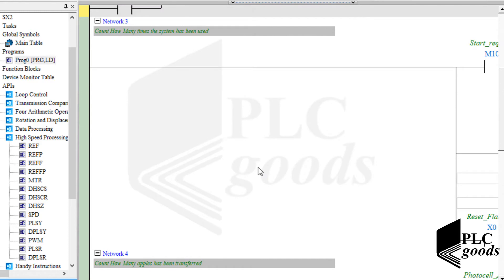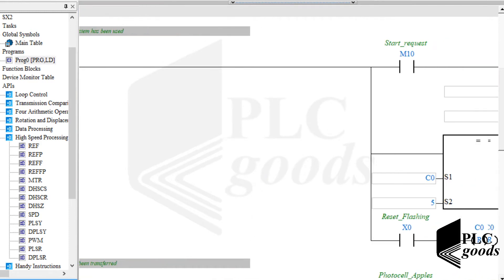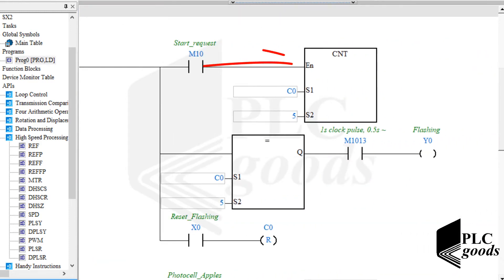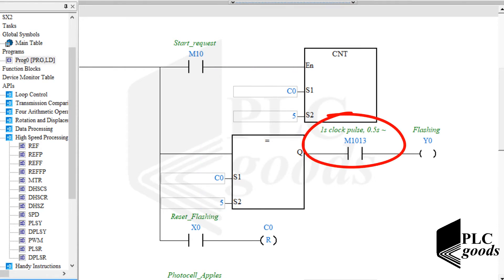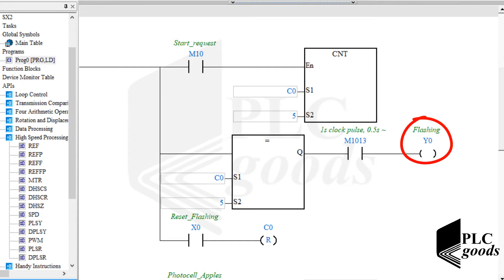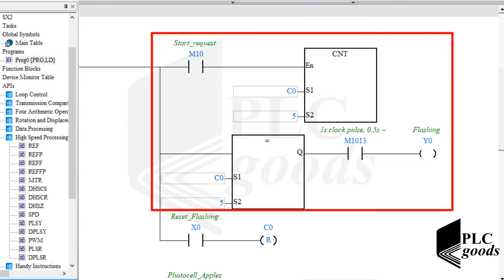Inside the next network, each start request will activate this 16-bit counter. Then after 5 start requests, because of this clock pulse memory which was explained before, this output will start flashing — because I assumed the system must be checked after every 5 start requests. Here I wanted to show you how counters can be used for maintenance purposes.